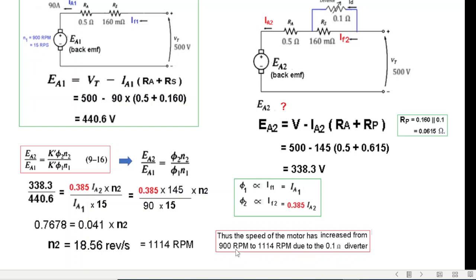The speed has increased from 900 RPM to 1114 RPM due to the diverter. By using a diverter of suitable resistance, we can control the motor speed and achieve the desired operating point. I hope you were able to follow — please let me know through your comments.